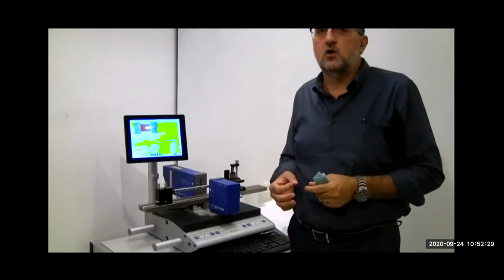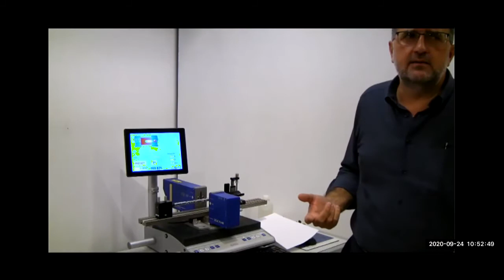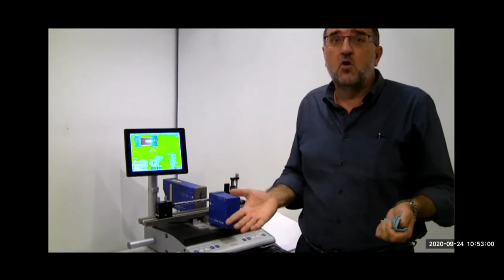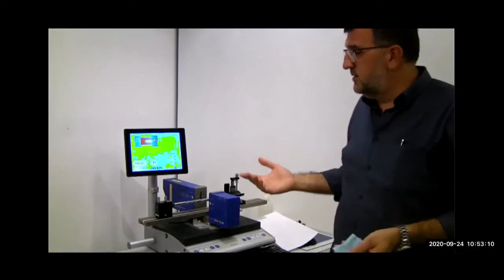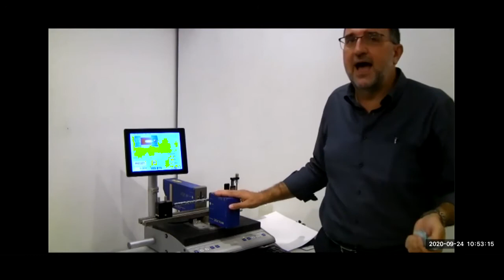The problem is that we don't have any type of problem with this type of motor. It's a motor with hard disk technology, so I think that every one of us has had a hard disk that was broken, but for sure the break was in some components of the electronics, and the motor continues to run without problem. The last model of motor that we use is starting from 10 years ago, I think, or more than 10 years. We mounted, I think, more than 6,000 motors. And of these 6,000 motors, we substituted only 2, maybe, for a shock, not for a problem, because there was an application in line, and so the laser sensor was bumped by something.